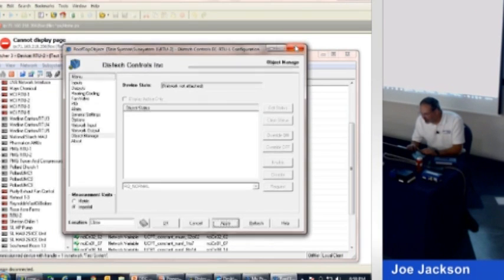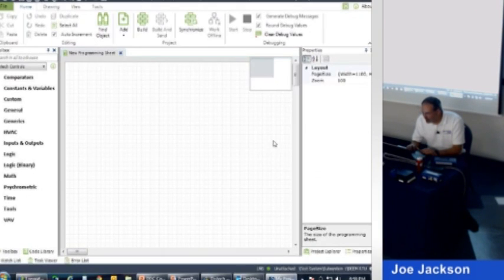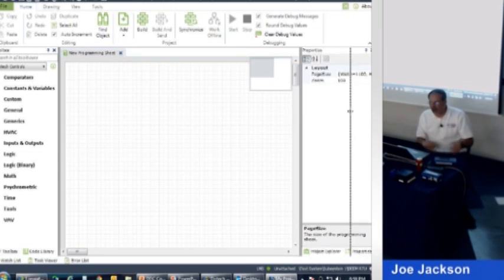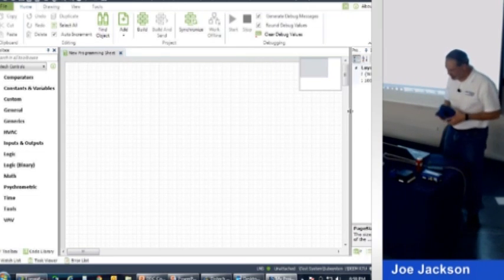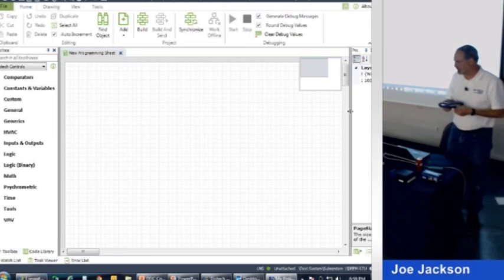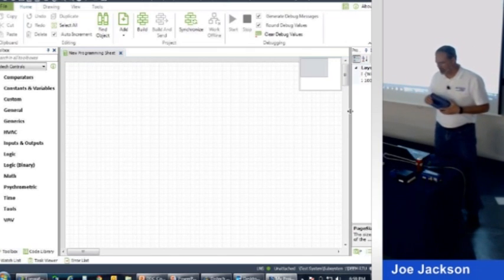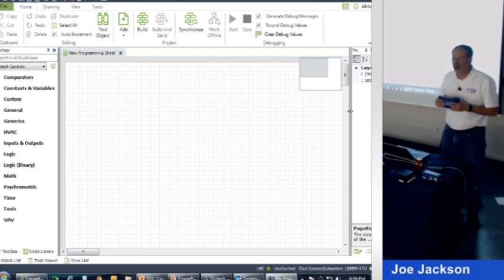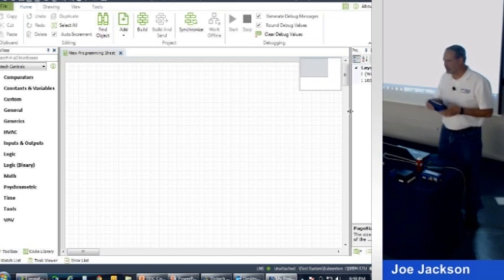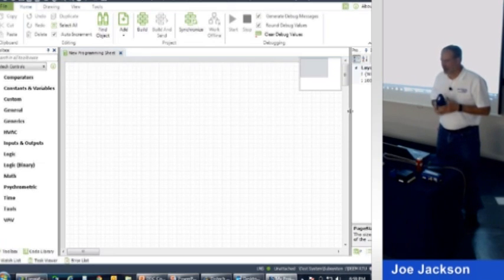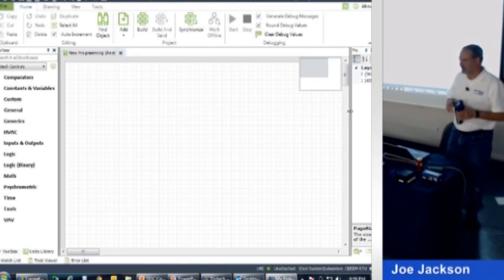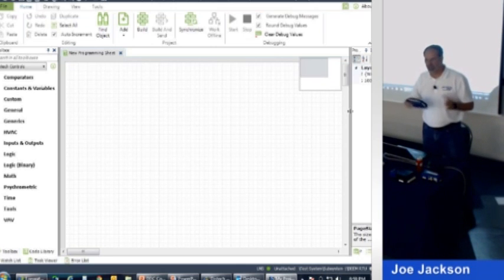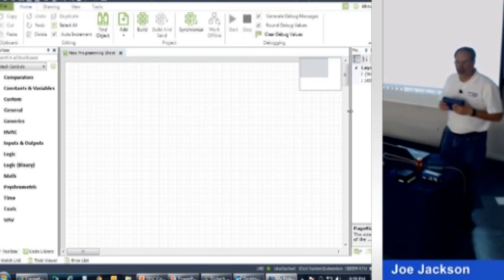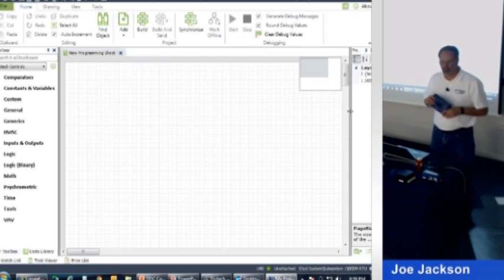And then the other type of controllers that we talked about are called programmable controllers. They can do whatever you want, and we're not going to spend a lot of time on them. If I were to write a program from scratch for a rooftop unit today, it would probably take me 20 minutes. So we don't ever write anything from scratch. If I'm getting ready to do a rooftop and I haven't done one lately, and I didn't save one in my system, I would go to one of my other guys and say, hey, do you have a standard rooftop? And they would say, sure, and they'd give me the file for it, and I'd load it in here, and it'd be 85% of the way done. I'd tweak it the way I want, and then I'm going to spend about 5 minutes setting it up.